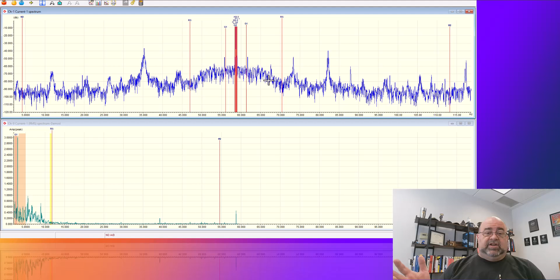Now I'm being told that a certain thing is wrong. I looked at the data and realized that somebody read a textbook somewhere and didn't understand that varying loads on a piece of equipment will vary your vibration readings, my frequency shifts. So I did take a look, and yes, this is actually only off by about point something percent. It's not much. It's allowed to get down a little bit lower, but they have a generator and everything else in a remote location. So their phase shift off of 60 hertz was pretty significant. We went in and verified it.